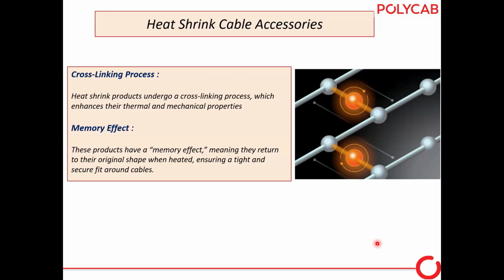A very interesting part of heat shrink technology is the memory effect. Many times you might have heard about the memory effect of heat shrink tubings. So what is the memory effect? When we send heat shrink tubes to site, they are in an expanded form, and when you give heat to the tubes, they shrink, up to the point we want or what we have designed. It's like I said in the last slide, 2 to 1. If I send a heat shrink of 100 by 50, it means 100 expanded and 50 after shrinking. So when we give heat, it shrinks up to 50 square mm only, not below 50 square mm. That's the memory effect.